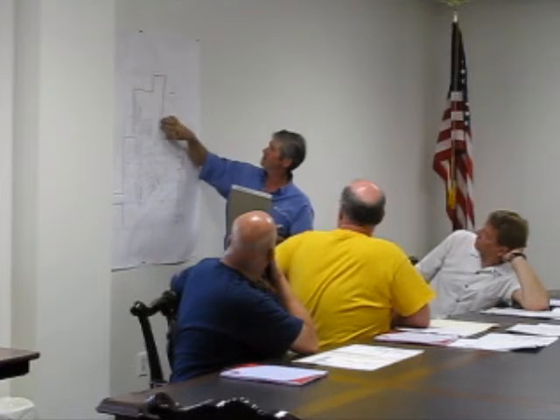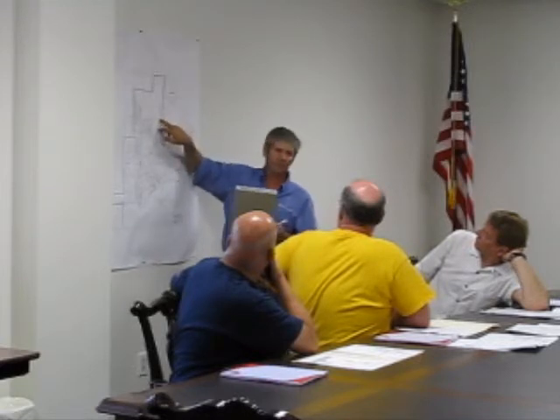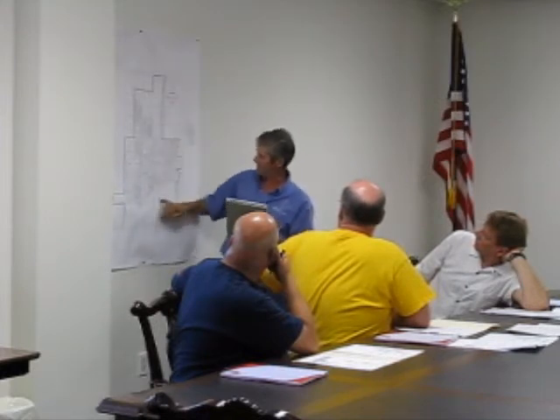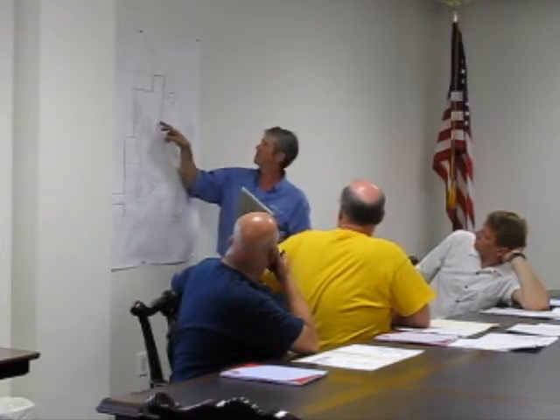We also have to watch so we don't overload that 1500 kVA transformer at the substation, because we got to go out to the other location, and that transformer is probably loaded about half now. The line coming from the sub all the way down here is heavy enough to handle about anything if we have a big enough transformer for the source.